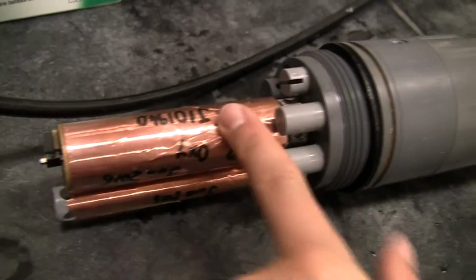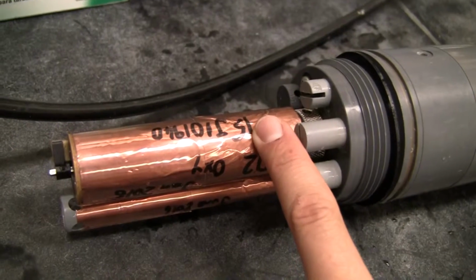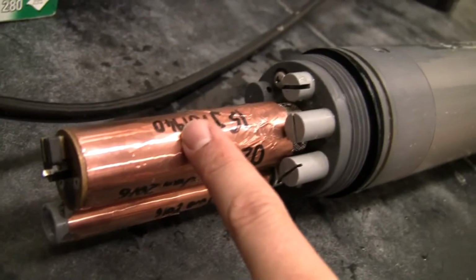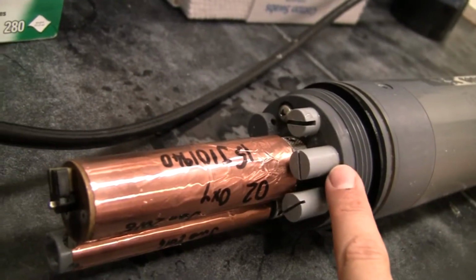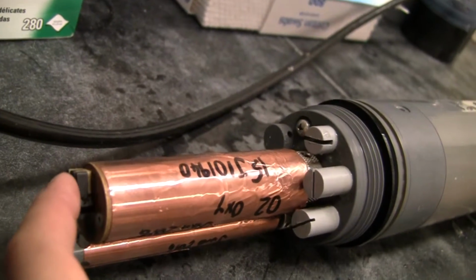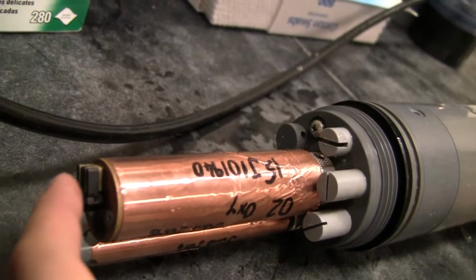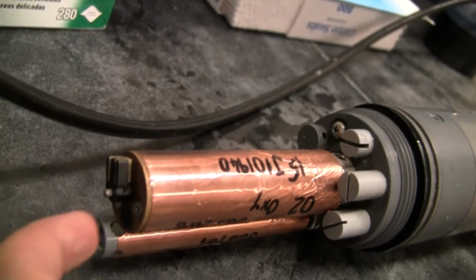That's this big sensor right here. This one happens to be wrapped in copper. That's just for anti-fouling. This is an optical sensor, which is in the largest port of this unit, and it has a wiper with a little bit of cloth that, when the sensor turns on, runs around in a circle and wipes the top clean.